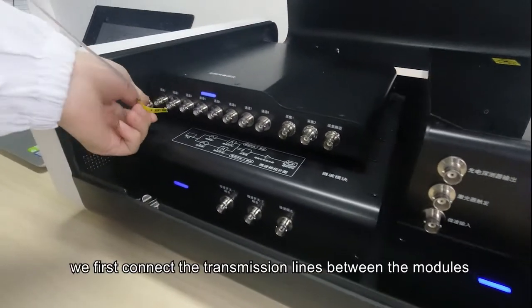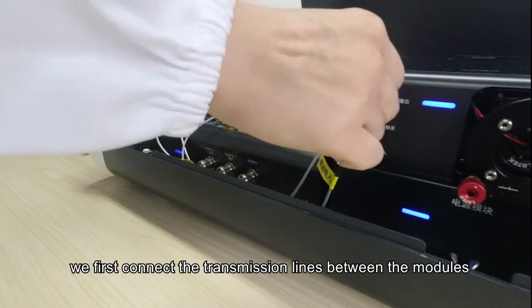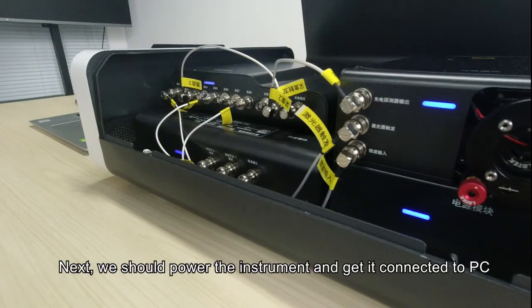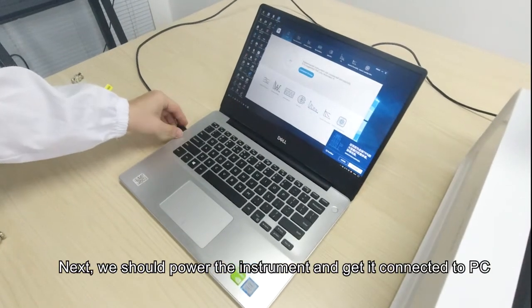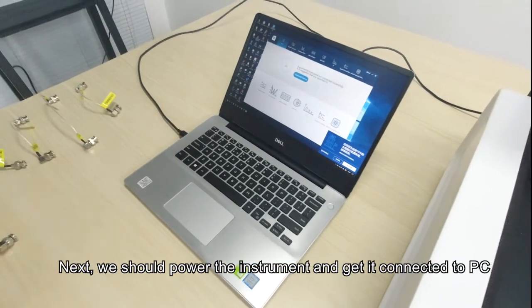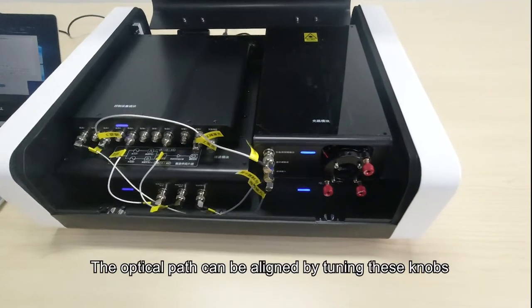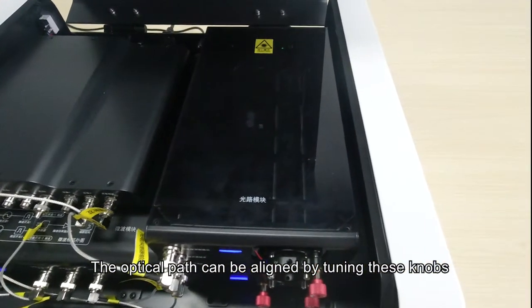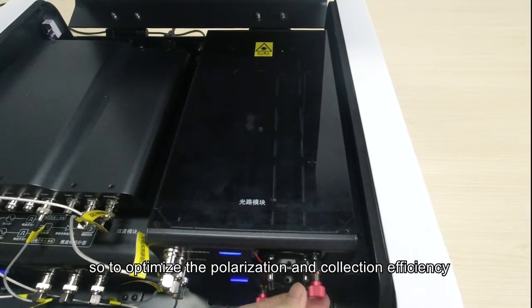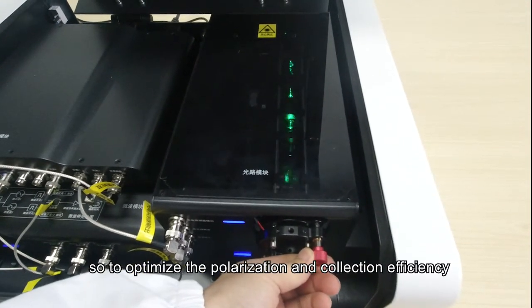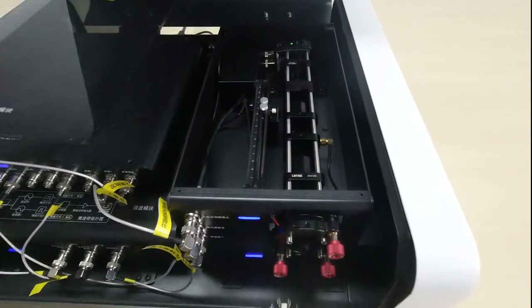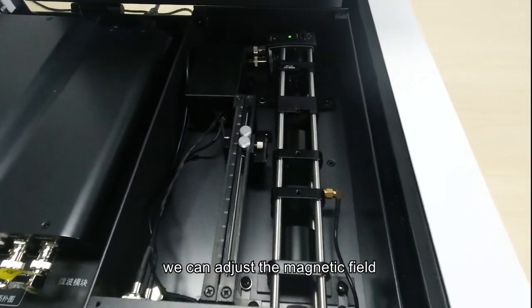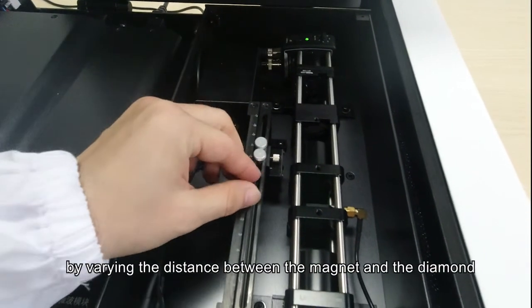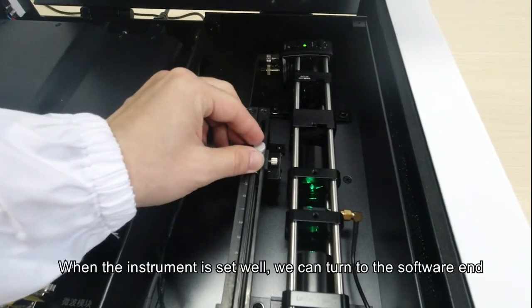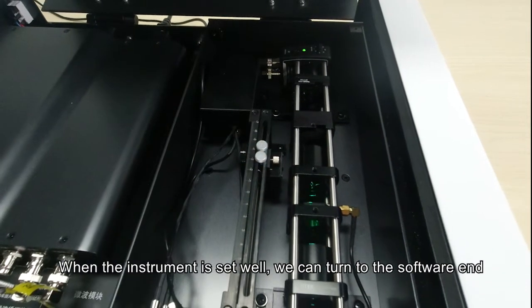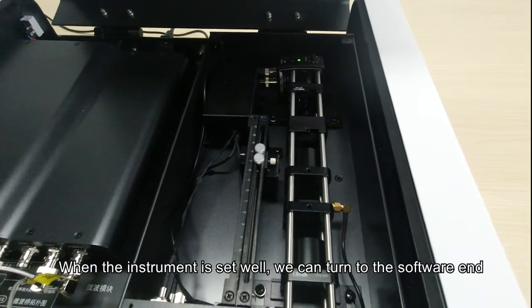To get started, we first connect the transmission line between the modules. Next, we should power the instrument and connect it to a PC. The optical path can be aligned by turning these knobs, so as to optimize the polarization and collection efficiency. Inside the optical module, we can adjust the magnetic field by varying the distance between the magnet and the diamond. When the instrument is set well, we can turn to the software end.